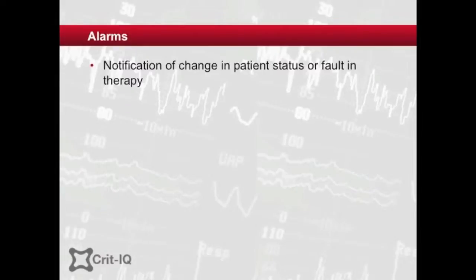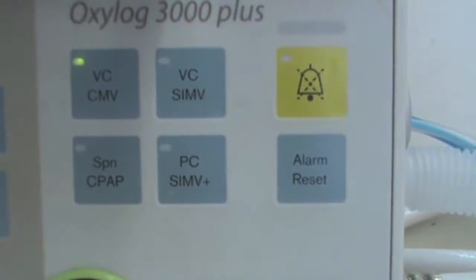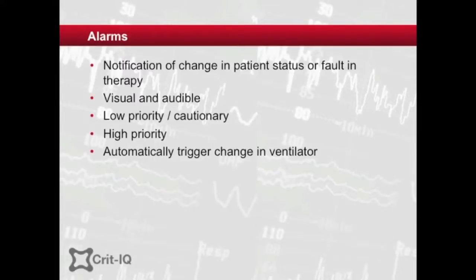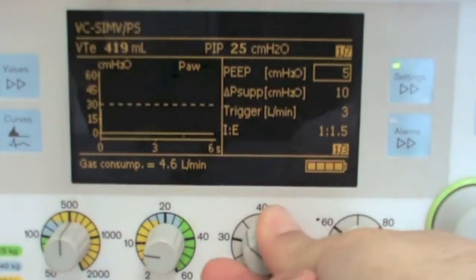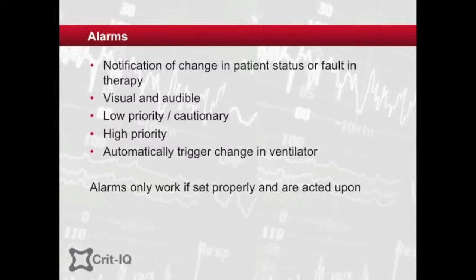As a warning tool, alarms need to alert the caregiver that something has changed. Alarms may be visual or audible, or both. Some are considered cautionary only, while others result in action by the ventilator regardless of whether or not they are noted, such as the high pressure alarm. Furthermore, many alarms can be tailored to the patient's needs and as such only function if set and monitored appropriately.